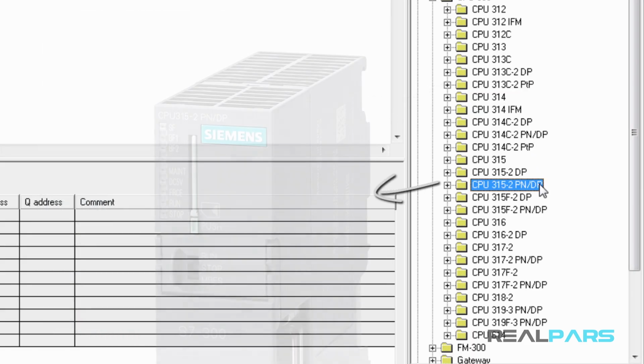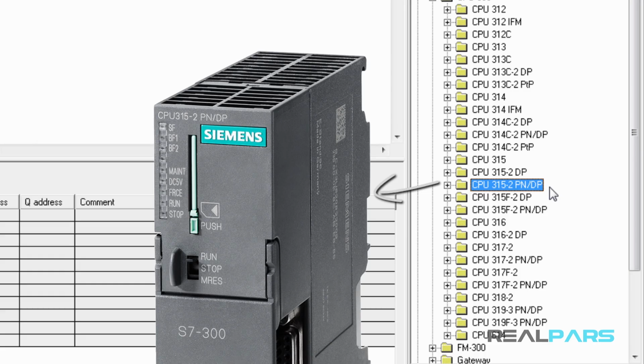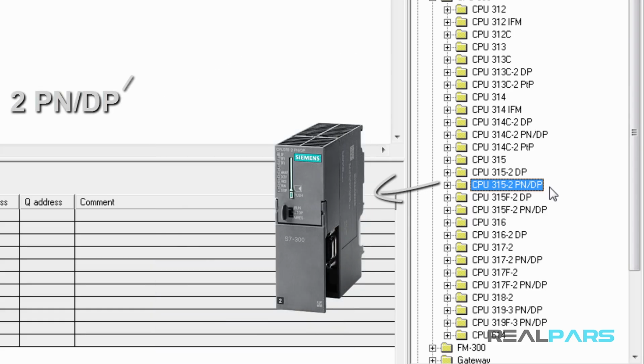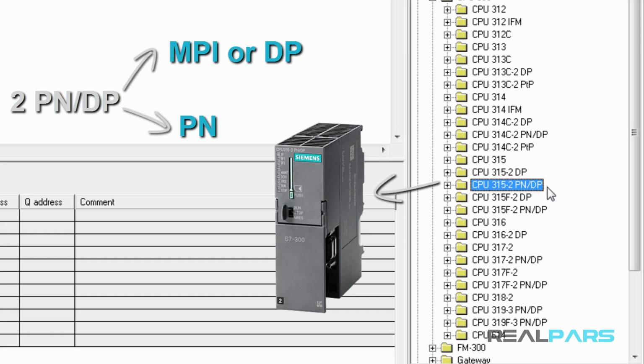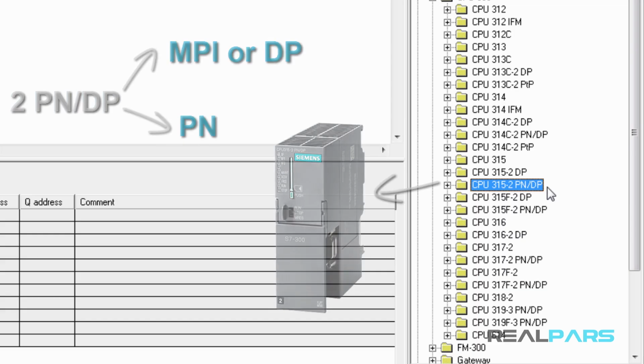CPUs like CPU 315-2 PNDP also have two ports. However, they are slightly different compared to the other CPUs because with these, the first port can also be used as an MPI port and a DP port, and the second port is the Profinet port, which we can use in an industrial Ethernet, also known as the Profinet network. Therefore, 2PNDP tells us that our CPU has two ports. The first port could be used as an MPI port and a DP port, and the second port could be used as a Profinet port.